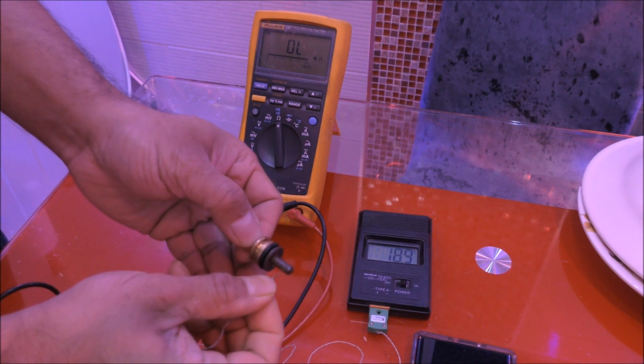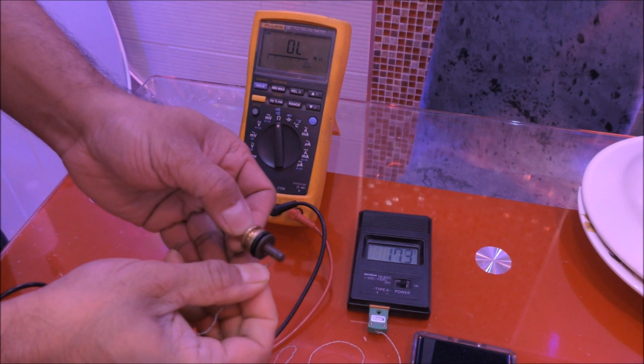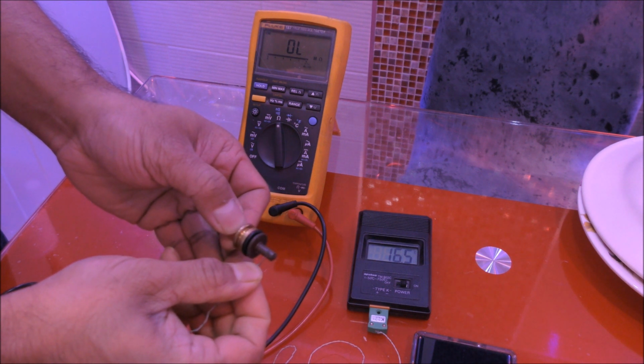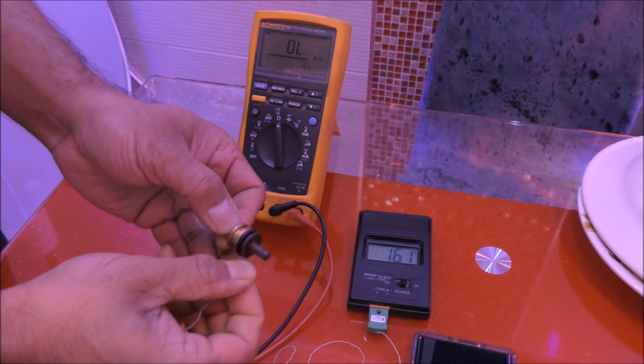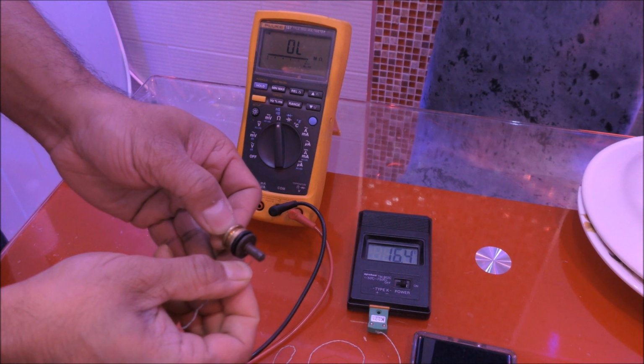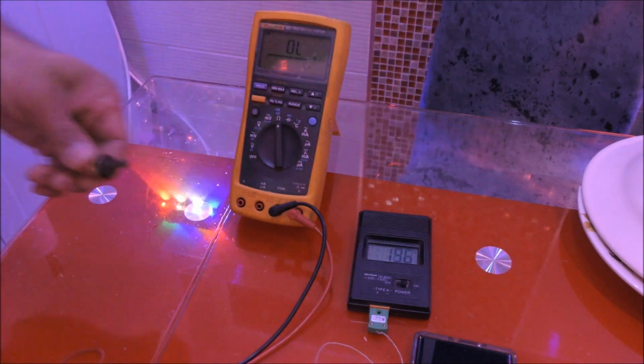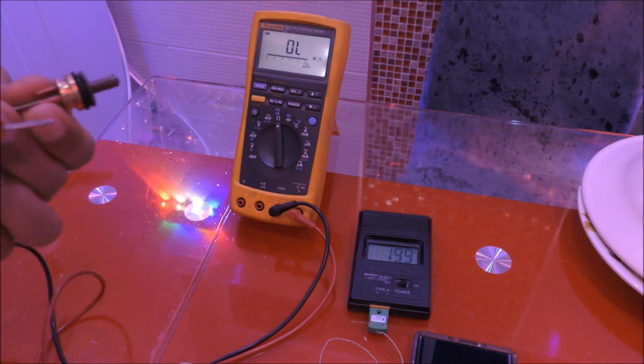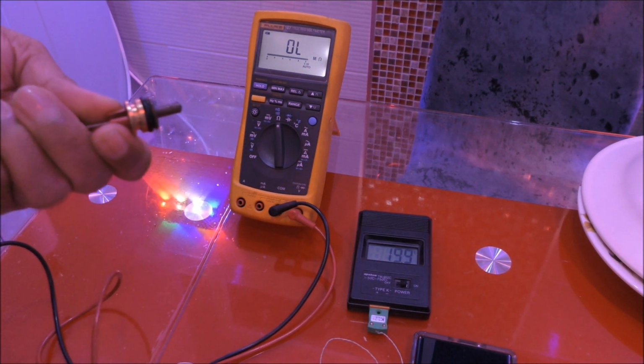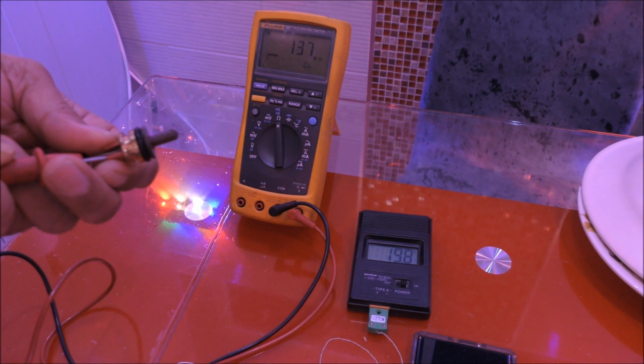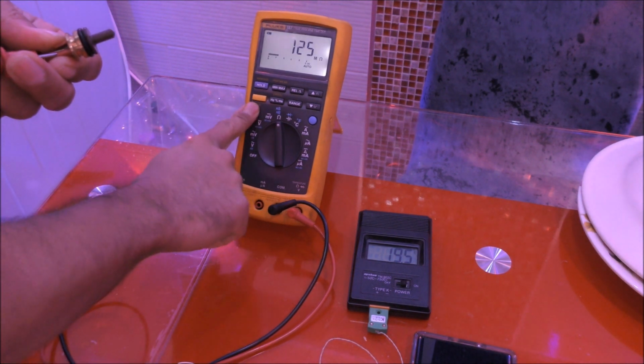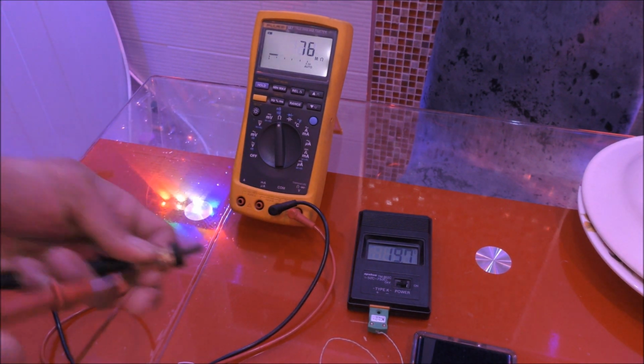All I'm doing is probing the top of that, and it's reading - let's just wait about 10 seconds - we'll call it 16 degrees Celsius at the moment. So very quickly, if it's 16 degrees, let me probe around and tell you the range - that's running about 12, 13. I have to be quick on that.